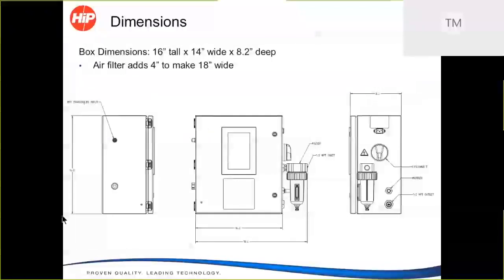From a dimensional standpoint, the unit's fairly small. It is approximately 18 inches wide, by about 16 inches tall, by about 8 inches deep. So the goal is to have a box that's fairly small in size, but very powerful, that can mount right to the wall, right to the side of an existing manual test bench, and not take up a lot of room. And just remember, by hooking up air and power to this unit and a pressure transducer, it's all you need to do to automate your pressure testing.